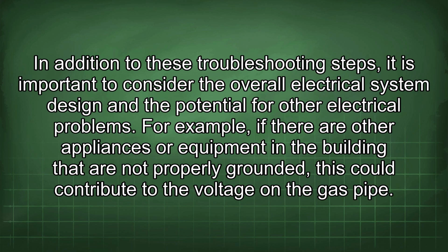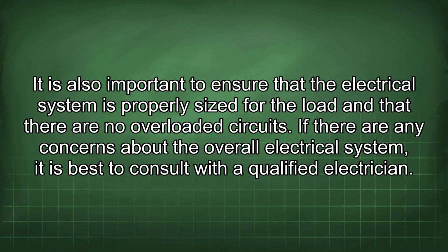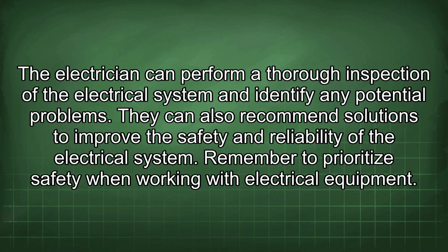In addition to these troubleshooting steps, it is important to consider the overall electrical system design and the potential for other electrical problems. For example, if there are other appliances or equipment in the building that are not properly grounded, this could contribute to the voltage on the gas pipe. It is also important to ensure that the electrical system is properly sized for the load and that there are no overloaded circuits. If there are any concerns about the overall electrical system, it is best to consult with a qualified electrician. The electrician can perform a thorough inspection of the electrical system and identify any potential problems. They can also recommend solutions to improve the safety and reliability of the electrical system.